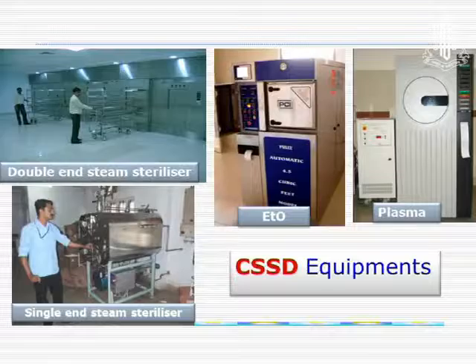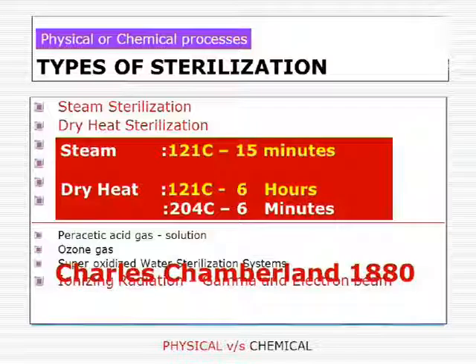These are the equipment used. Coming to the types of sterilization, we have physical as well as chemical. We will deal mostly with steam sterilization. Note that 121°C for 15 minutes is sufficient with steam, whereas in dry heat it is 121°C for six hours. Air is a poor conductor of heat, so a very high temperature is needed to achieve the same standard of sterilization.